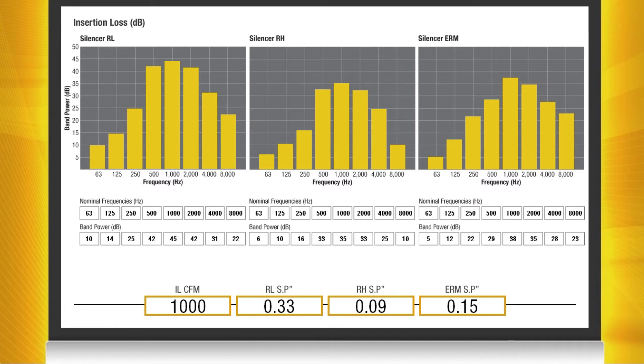This is something to keep in mind when selecting silencers. It's always a balancing act between insertion loss and pressure drop. The more sound that you want to remove from a duct system the more pressure drop you're going to have to deal with.